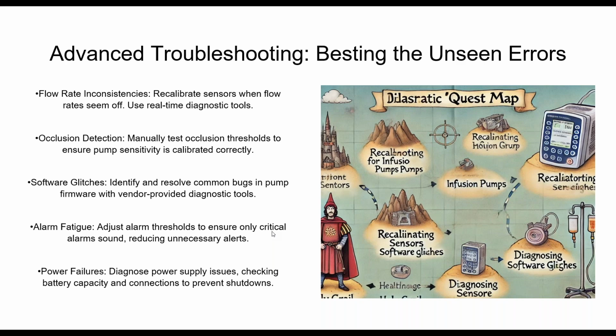As a matter of fact, I'm going to make a note of that real quick, because this is something I'll add to the top 10. When something comes back from the manufacturer or from a third-party service provider, make sure you put your settings back on that pump. They are very likely to have erased your settings as part of your acceptance before it goes back on the floors. Make sure you put those things back on.